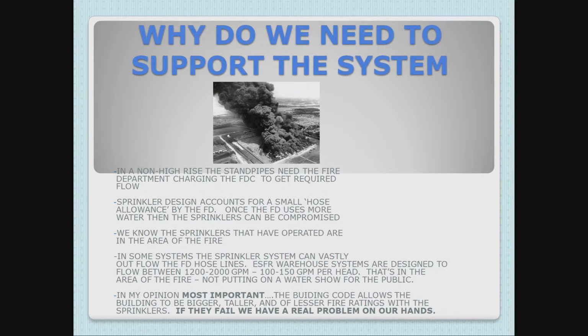The building, again, it's going to be bigger between firewalls. It's going to be taller than it would have been allowed to be built without sprinklers. The fire ratings are going to be reduced because they're going to be able to use a different construction classification for the same size building. All those things combine that if the sprinklers don't control the fire, we have a genuine issue. So this is the why of it. So I want to talk about, so what do we do if we come and we go to use the FDC and it doesn't seem like we're getting any action out of it?